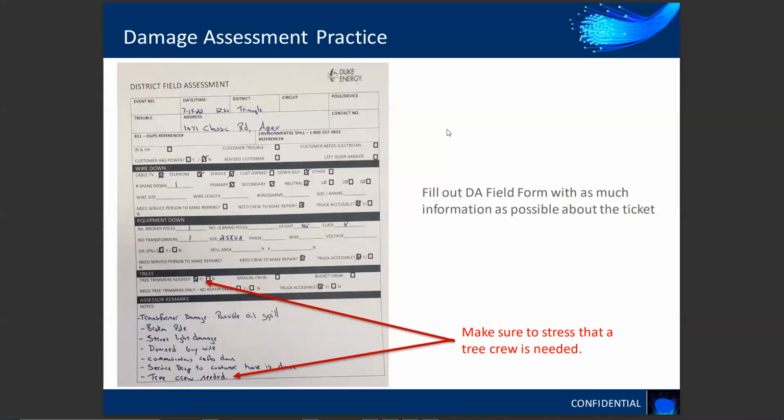And I have had to physically walk a mile in a back area setting, because the primary lines went through a set of woods, and we had to trace the line, what was going down. We didn't see a line down until about 3/4 of a mile, but we did see other damage. There were poles that were leaning. There were some cross arms that were broken.